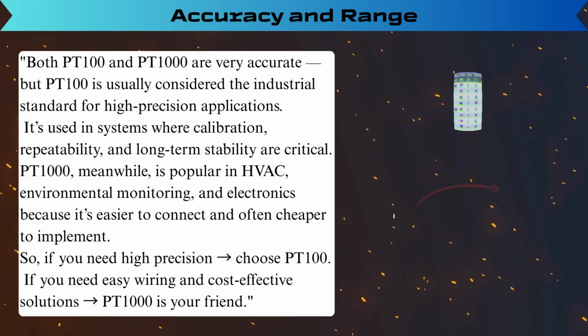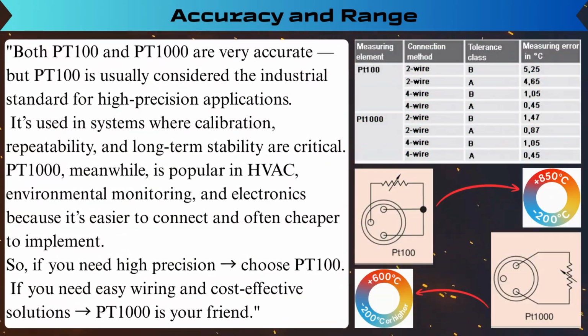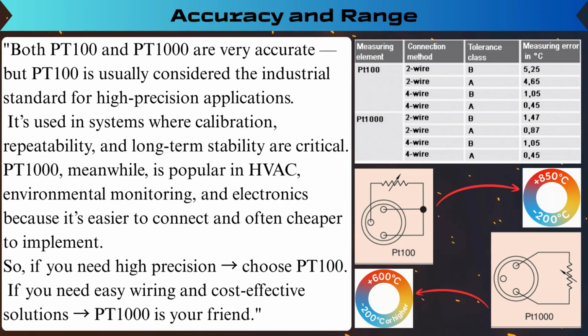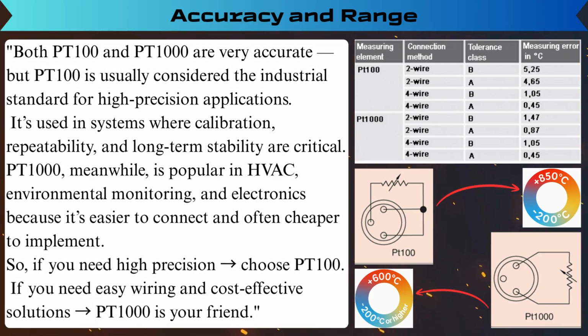installations. Accuracy and range. Both PT100 and PT1000 are very accurate, but PT100 is usually considered the industrial standard for high-precision applications. It's used in systems where calibration, repeatability, and long-term stability are critical. PT1000, meanwhile, is popular in HVAC, environmental monitoring, and electronics because it's easier to connect and often cheaper to implement. So, if you need high precision, choose PT100. If you need easy wiring and cost-effective solutions, PT1000 is your friend.